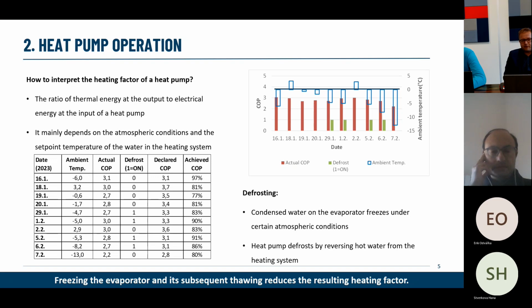The heat pump also performs so-called defrost. So especially when you run around and below freezing point, because the evaporator actually extracts the heat from the ambient, it starts developing an ice on the evaporator. And you may see lots of heat pumps failing because they do not perform the defrosting properly, and then the heat pump can go actually in a failure. So it's important to actually check that the heat pump performs that, but essentially it decreases the actual coefficient of performance, because the heat you would have otherwise delivered to the dwelling or to your plant, you have to use for actually de-icing, defrosting the evaporator.